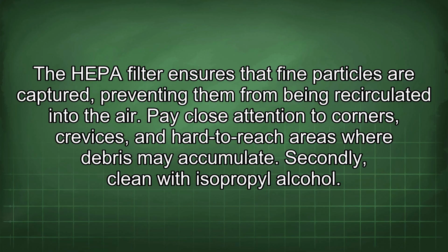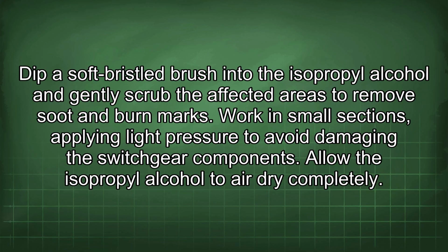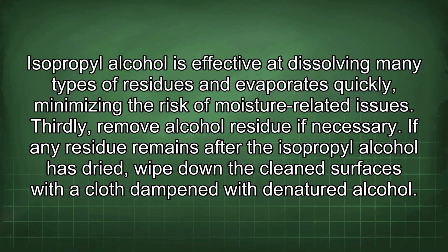Secondly, clean with isopropyl alcohol. Dip a soft bristle brush into the isopropyl alcohol and gently scrub the affected areas to remove soot and burn marks. Work in small sections, applying light pressure to avoid damaging the switchgear components. Allow the isopropyl alcohol to air dry completely. Isopropyl alcohol is effective at dissolving many types of residues and evaporates quickly, minimizing the risk of moisture-related issues.